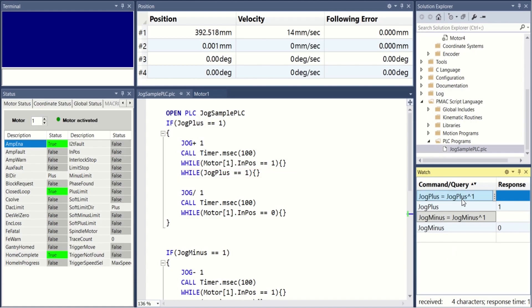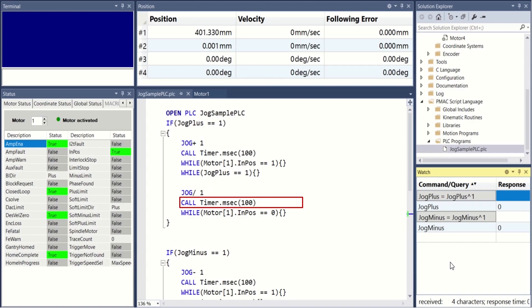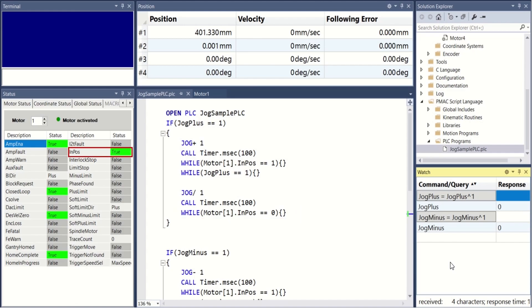As soon as jog plus is released, the jog slash command is issued followed by a 100 millisecond time delay. The ensuing while loop waits for the in position bit to be set, indicating that the motor has come to a stop. This protects the process against mechanical or electrical switch hysteresis.